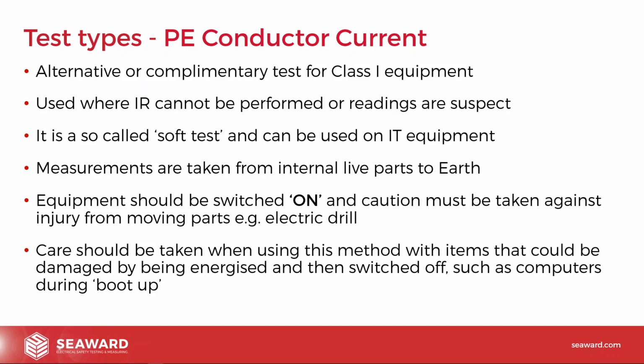Now, again, you can get some equipment where it naturally has leakage current anyway. There might be components between the line or the neutral to earth, and you will naturally then see some leakage in there. Computers and things like that generally have natural leakage currents. So it doesn't mean that the second you see any leakage current that there is a problem, but there are limits. And in the current code of practice for something like portable or handheld equipment, it's 0.75 milliamp for class 1 equipment.